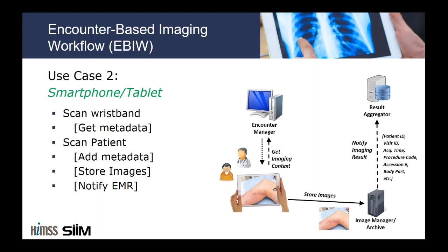So moving on to a third possibility, you may have a camera which is also using proper cameras, proper lighting. Perhaps you're taking mole pictures. In the same way, if you brought somebody into the CT suite and you asked them to point at the modality, most people would point at the gantry. And in fact, from DICOM terms, the modality is the console. It's the operator console of the CT that does the modality work list query and forms the images up into DICOM and pushes them off to the archive.